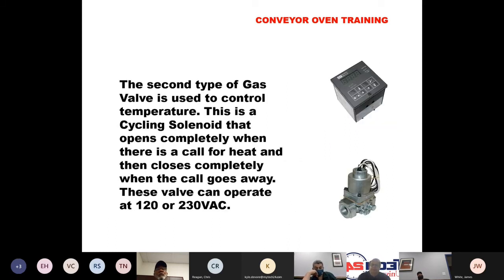The second type of valve is used to control temperature. We refer to this valve as a cycling solenoid because it opens completely when there's a call for heat, and then closes completely when the call goes away. These valves can operate at 120 or 230 volts AC. If you see one of the valves in the bottom right with the black and white wire, that's a 120 volt valve. If you see one with a yellow and black wire, that's a 208, 230 volt valve.